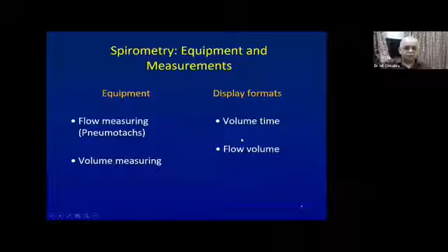So these signals, flow and volume and time, can be displayed in two ways. See, our display is X versus Y, or on two axes. So either it can be volume versus time or flow versus volume. Each has its plus points, and in normal functioning, we obtain both the tracings or both the printouts from the same maneuver. So the patient need not do it twice, because our equipment is made in such a way that it will give you both volume-time and flow-volume curves in the same maneuver.